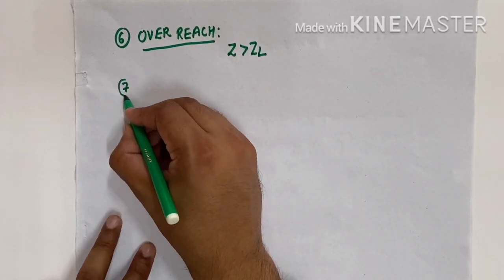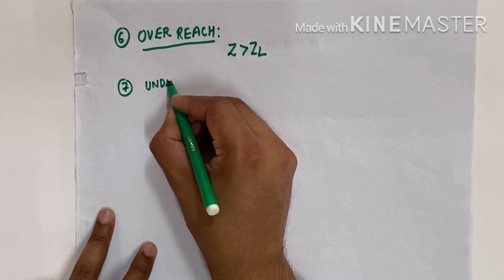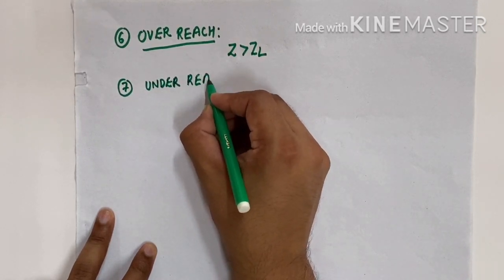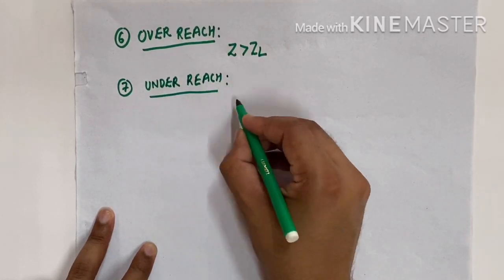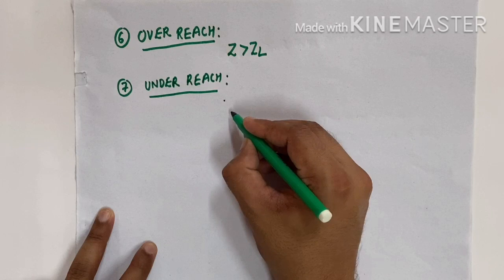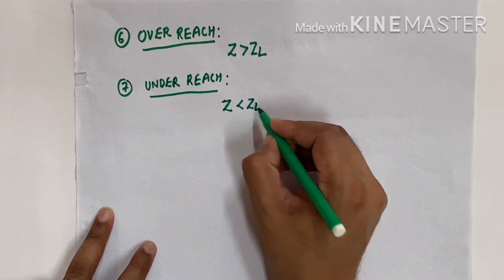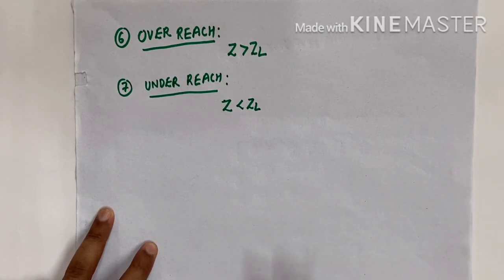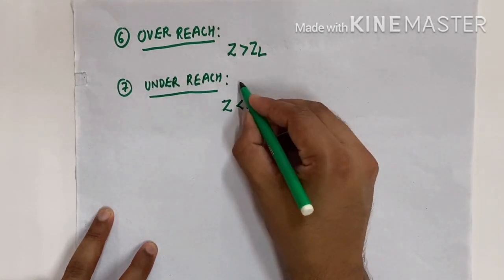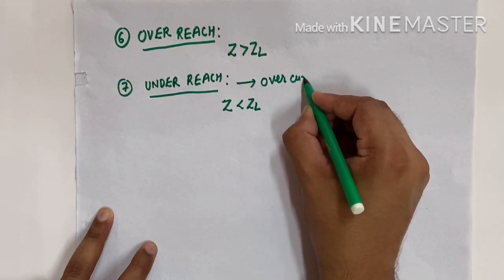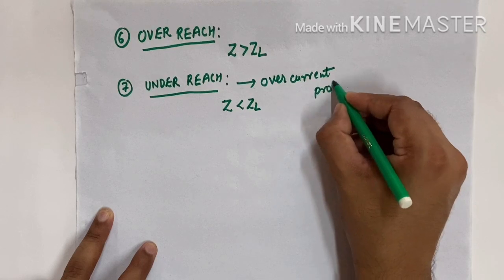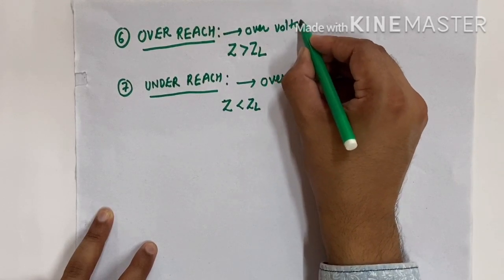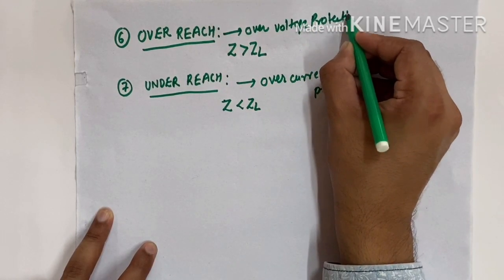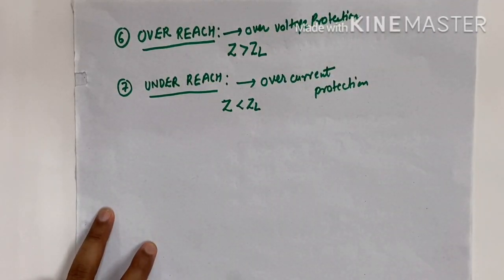Now after overreach there is the underreach concept. What is underreach? Underreach means that the relay is set for the operational condition Z less than ZL. If Z is less than ZL, this is used for over current protection, and the other is used for over voltage protection. Overreach is related to over voltage, underreach is related to over current protection.